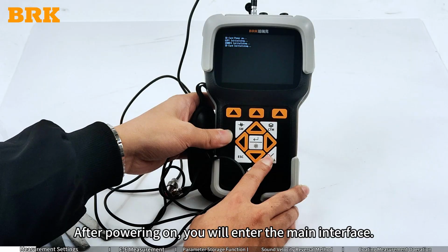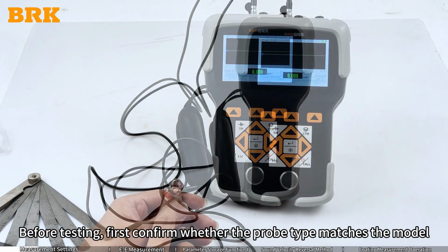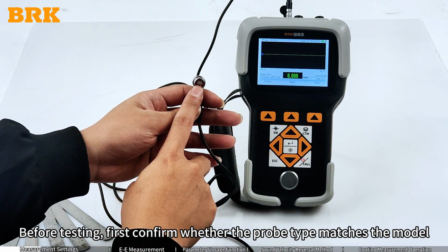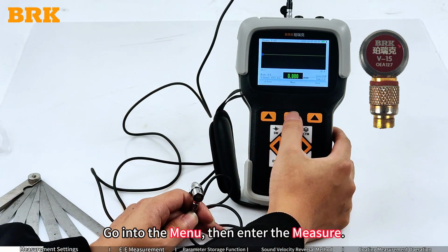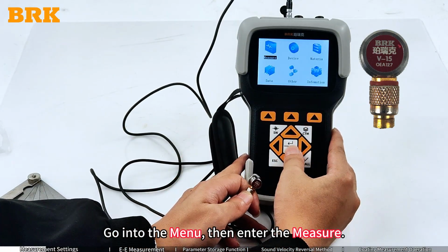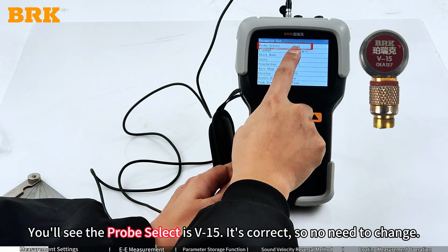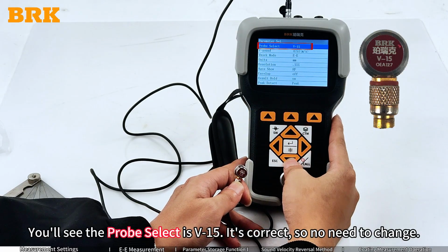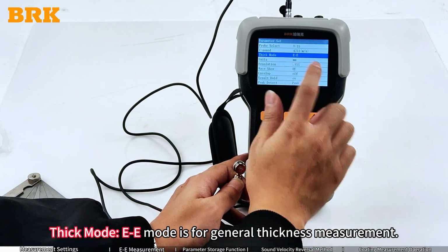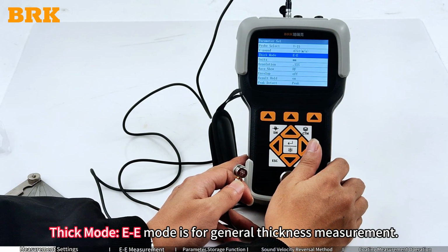After powering on, you will enter the main interface. Before testing, first confirm whether the probe type matches the model. Go into the menu, then enter the measure. You'll see the probe type is V15. It's correct, so no need to change. Thick mode, EE mode is for general thickness measurement.